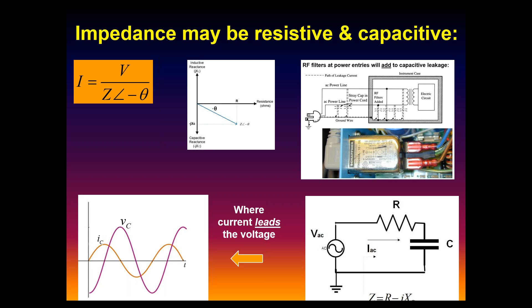So for example, with 10 nanofarads of stray capacitance, 10 to the minus 9, a small amount of capacitance between the hot side and the case, that 10 nanofarad capacitor looks like a 265 kilo-ohm resistor. So if you put a 265 kilo-ohm resistor between the hot side of the line and ground, you're going to create a leakage current of 452 microamps. That's what you would literally measure with your safety analyzer if you plugged in a device with that kind of capacitance.